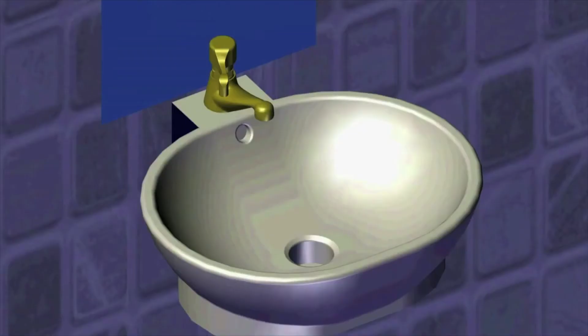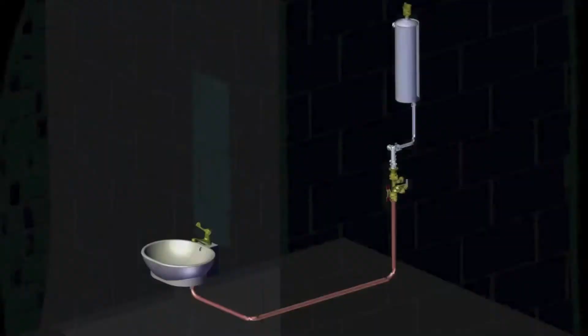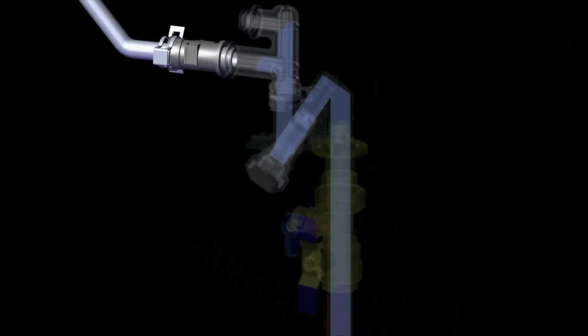When the consumer uses domestic hot water during central heating mode, central heating is temporarily stopped by the movement of the three-way valve to divert the heated water to circulate back through the internal storage tank, providing priority and large amounts of domestic hot water production.